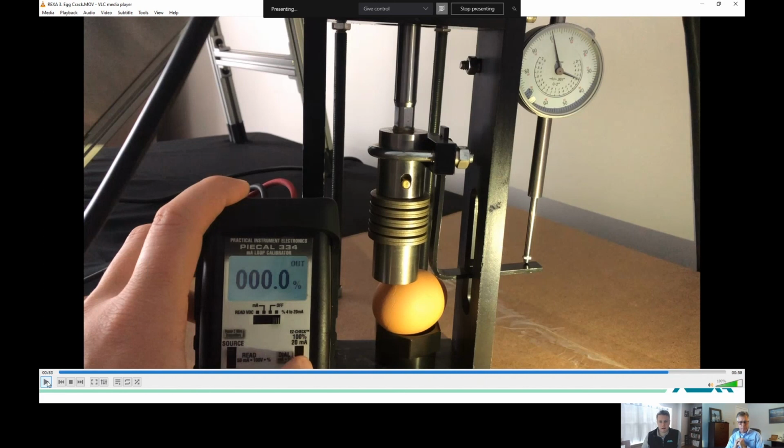Yeah, so the REXA linear actuator we're demonstrating with is an L, for linear, 2,000 pound thrust actuator with 2 inches of stroke. We can do up to a linear 120,000 pound thrust actuator, and we've done over 100 inches of travel in water hydro plant applications or large gate valve applications. On the rotary actuators, we'll start at 2,500 inch pounds of torque and go up to 400,000 inch pounds, and we've done 1 million inch pounds of torque. Typical 400,000 inch pound applications include ID fan dampers and large rotary valves for pipeline industries.